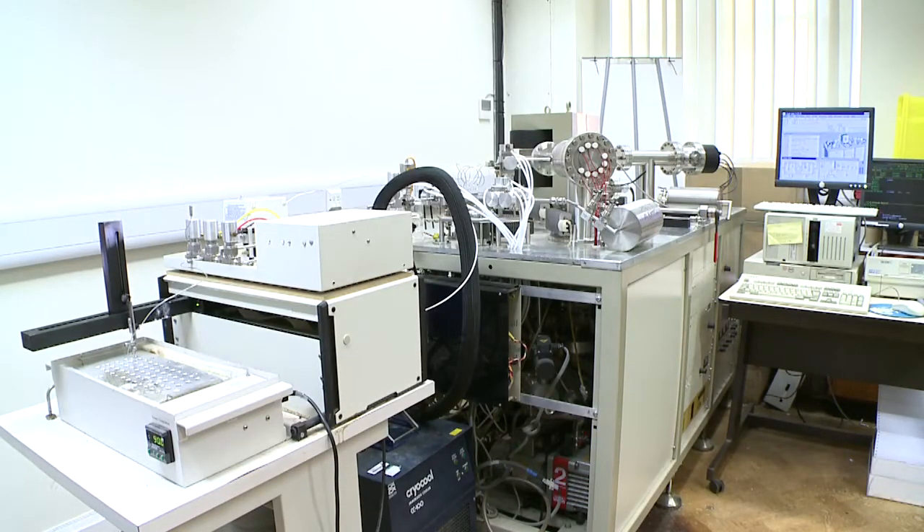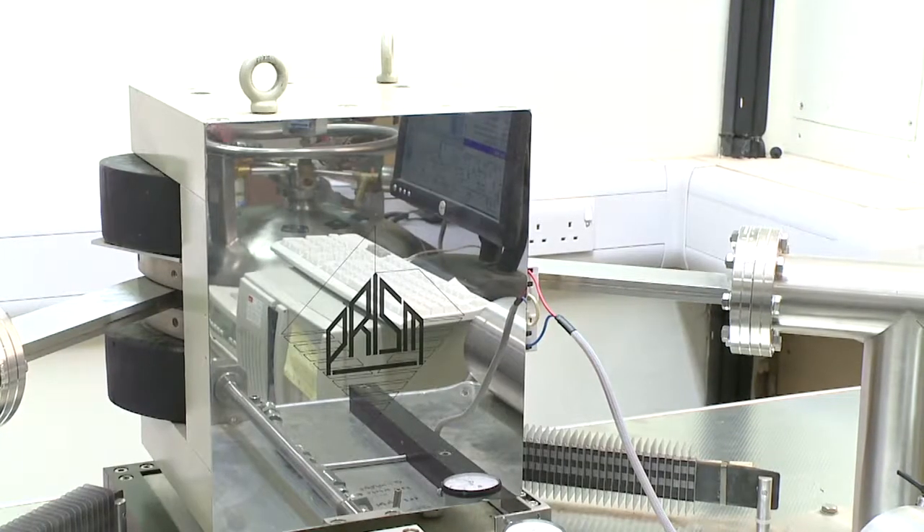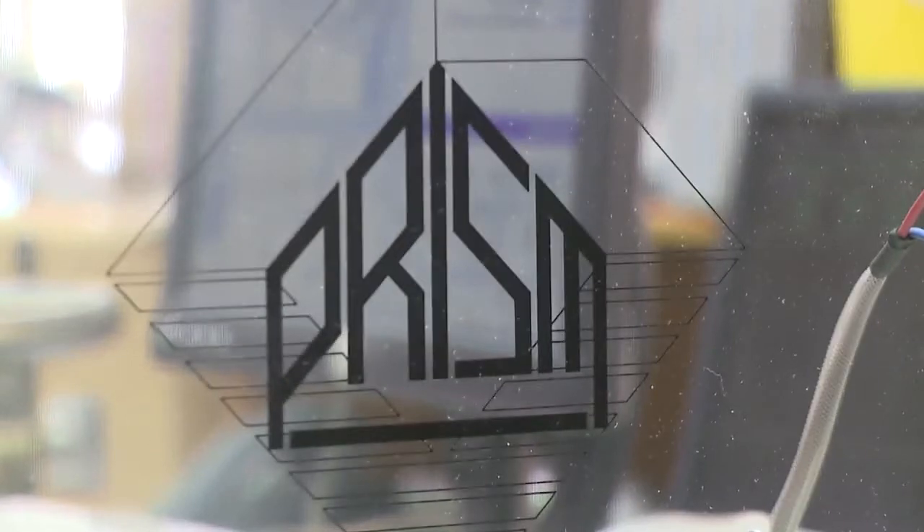There are three main parts of the mass spectrometer: the source, the flight tube, and the magnet and collector arrangement. You can see that they go around in an arc. The CO2 gas produced from our samples is put into the mass spectrometer in what's called the source, where the gas is ionized by heating a filament. A beam of electrons goes in a spiral across a box and ionizes — or knocks off electrons from — various molecules inside the box. These molecules are then accelerated with a potential difference of about four and a half thousand volts and drawn out of the source into the flight tube of the mass spectrometer.